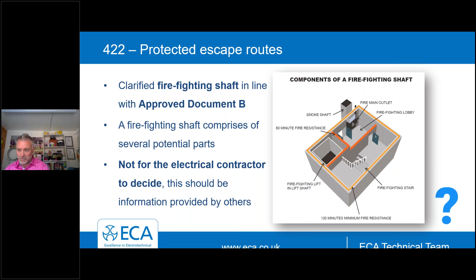So you will note here that we've got clarification of what a firefighting shaft is, and that's in line with Approved Document B, BS 9991 and BS 5839. What's really important here is that the fire engineer specifies the classification of the protected escape route. It's not up to the electrical designer. And you can see the different elements here and the components of what we call a firefighting shaft.